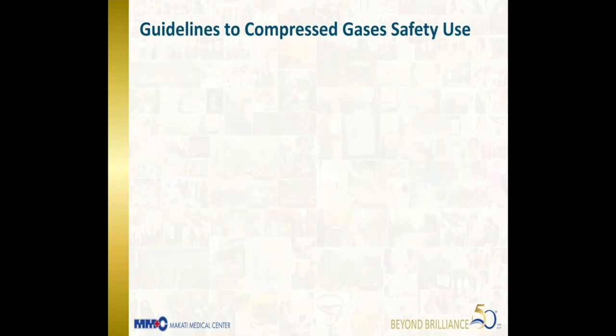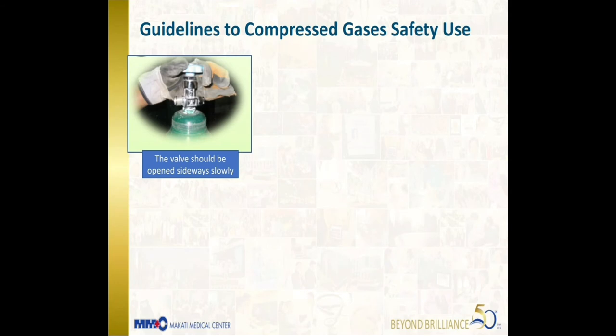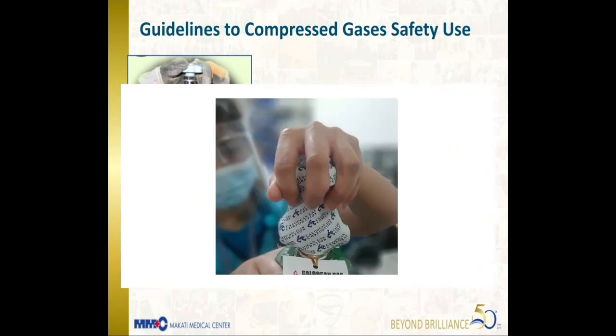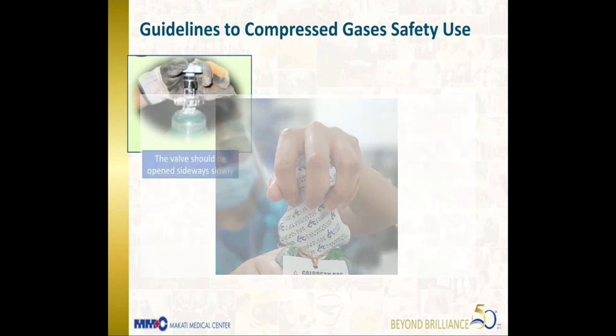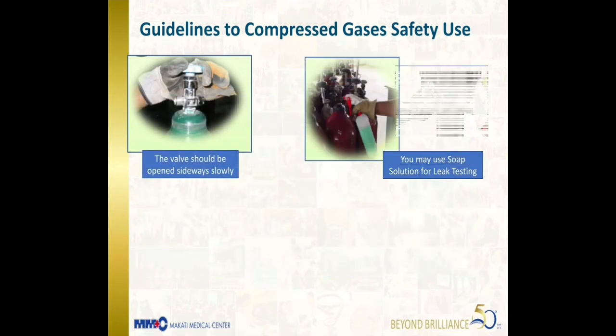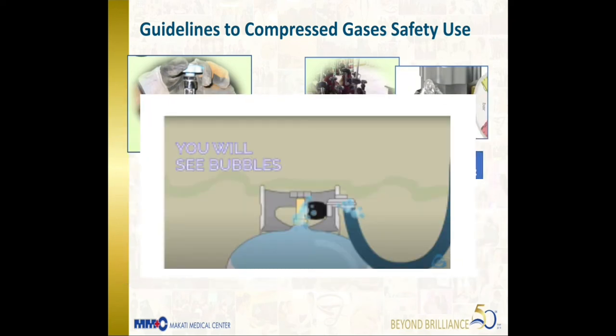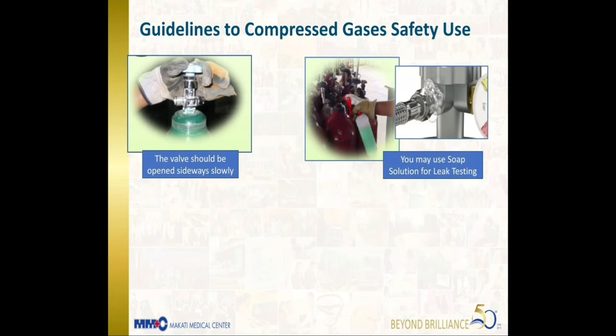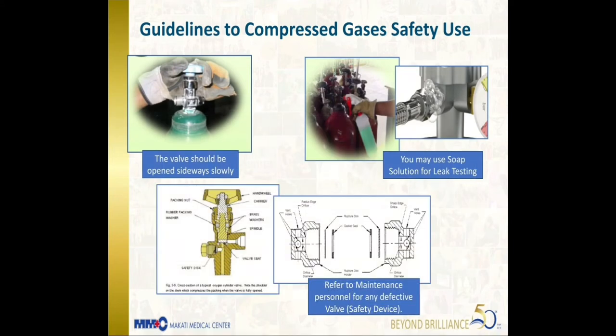The valve should be opened sideways slowly. Opening or closing the valve with a hand on top of the wheel is not recommended. You may use a soap solution for leak testing — bubbles that appear around the potential area will indicate a leak. Refer to maintenance personnel for any defective valve.